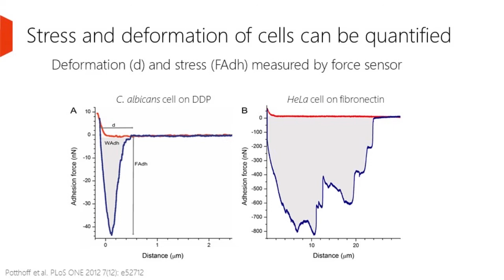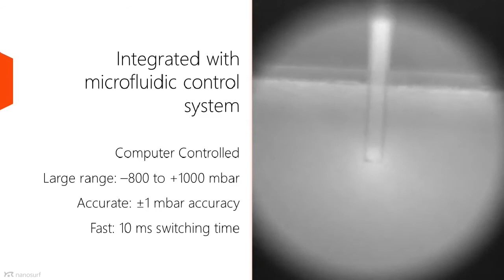The last part of the FluidFM system is that it's integrated with a microfluidic control system. Now, this is computer controlled. It gives you a large range of positive and negative pressures, so you can pick up cells or deposit them. It's fast. As you can see on the video on the right, we have a fluorescent dye inside the microfluidic channel, and there are pulses pushing this dye out through the aperture in the front of the microfluidic channel. Everything together makes the FluidFM a miniature pipette tip.